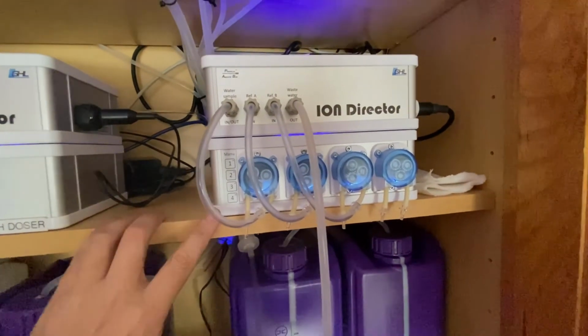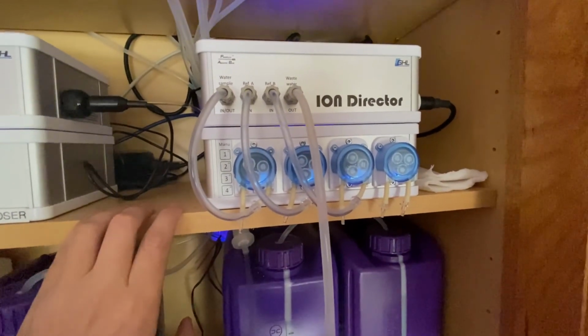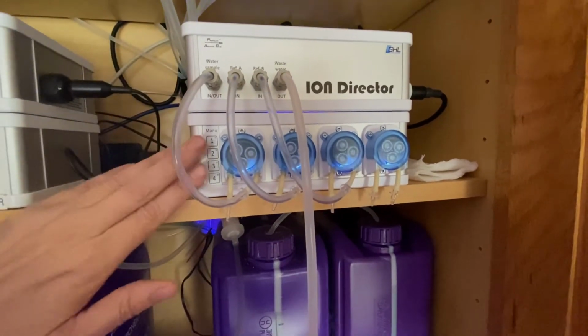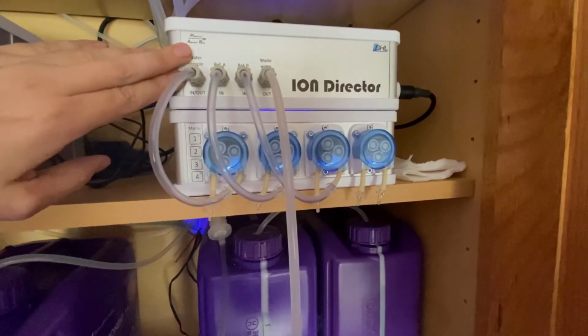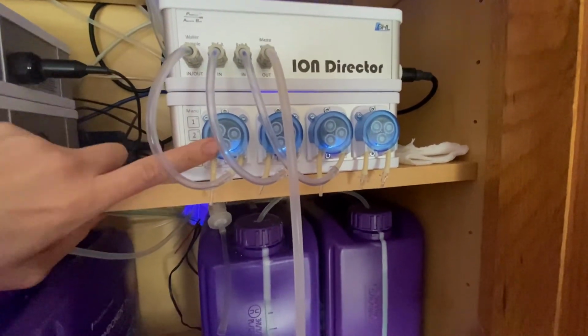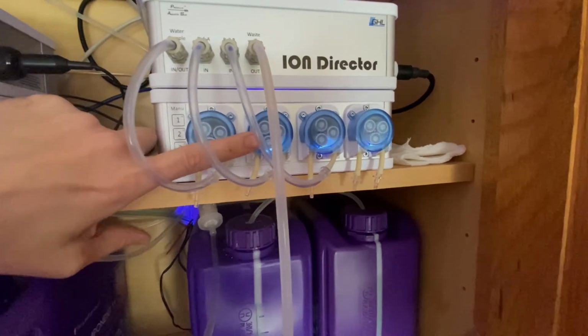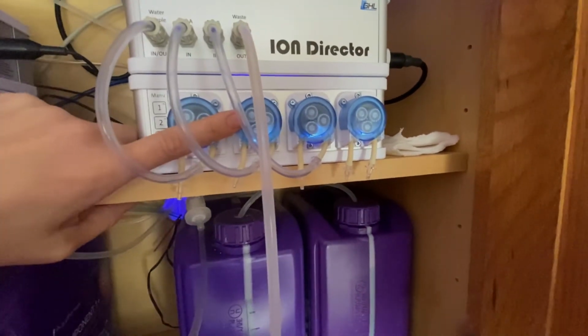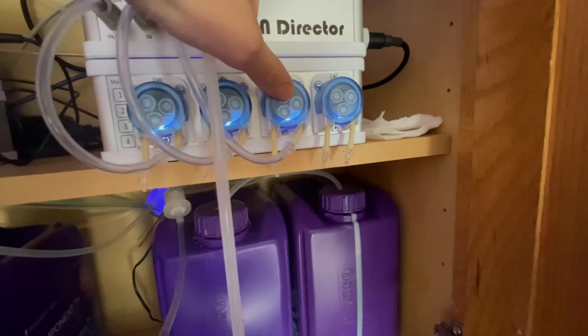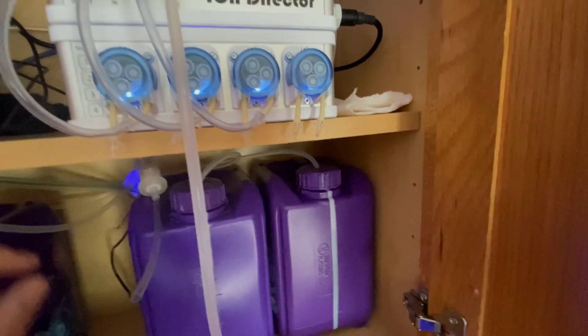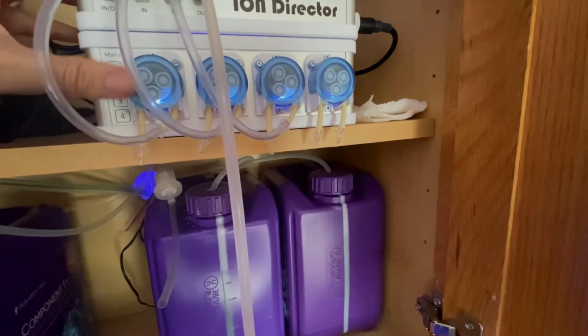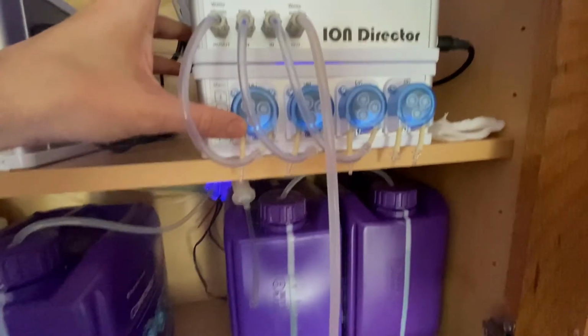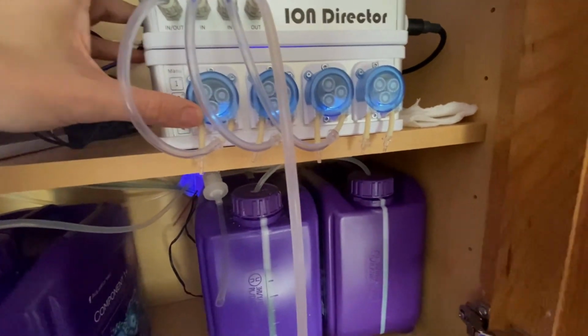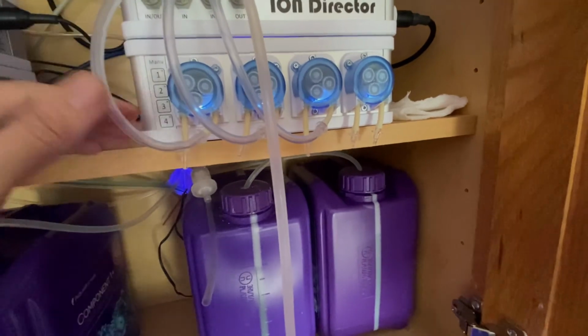Okay, with the pumps now calibrated, I can now connect all the interconnecting tubes between the doser and the ion director. Understanding that this is my water sample pump, this was my reference A pump, and this is my reference B pump. So from the water sample pump to pump A, or the first doser pump, I've connected the water sample tube.